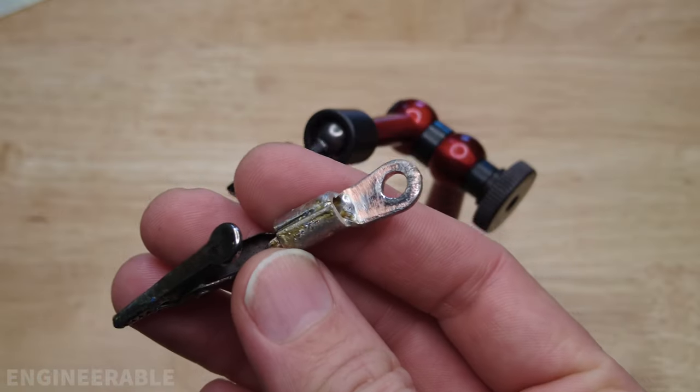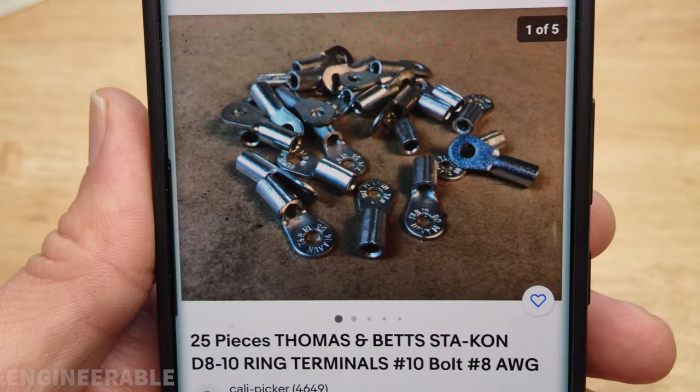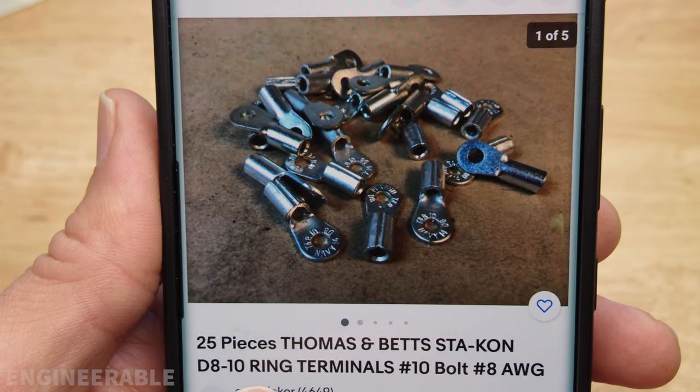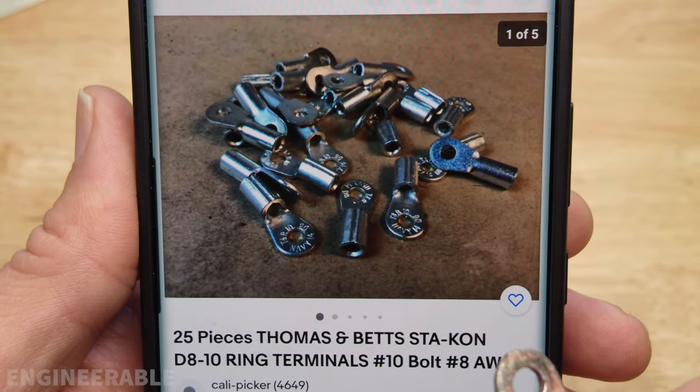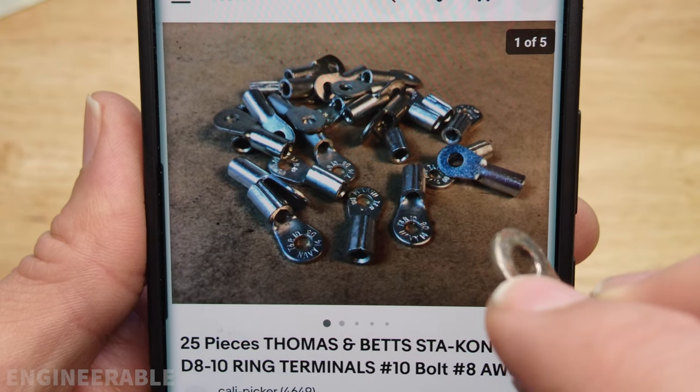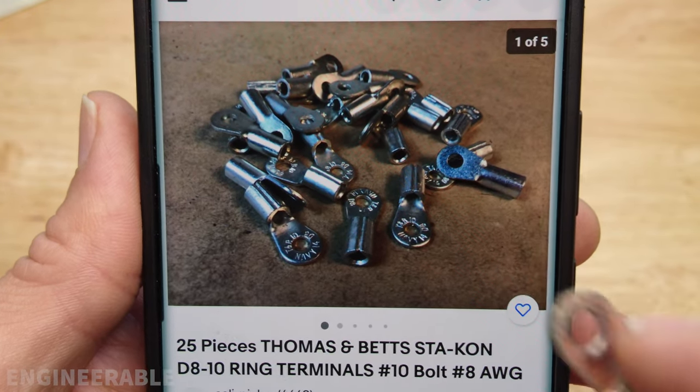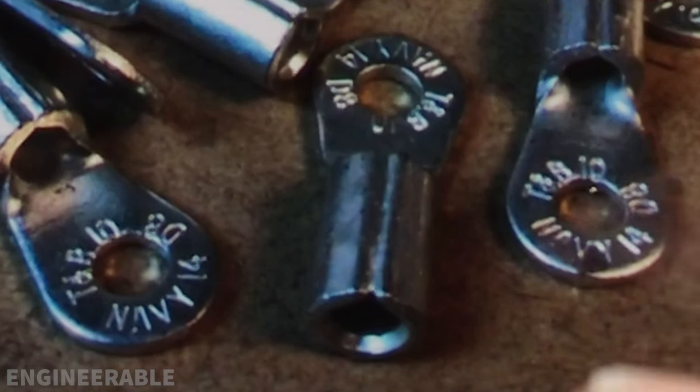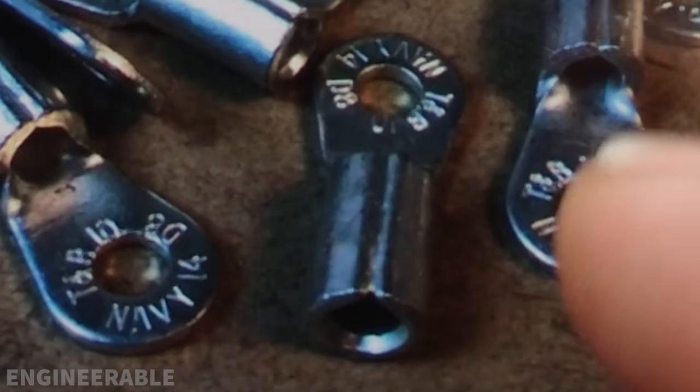This ring terminal that I used here is a Thomas and Betts D8-10 ring terminal, which means it's designed to fit a number 10 bolt through this hole, which measures about 0.1875 inches, and it's made for 8 gauge wire. The markings on the terminal said Navy 14 D8-10.